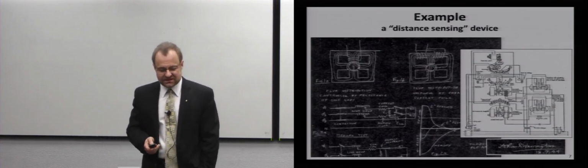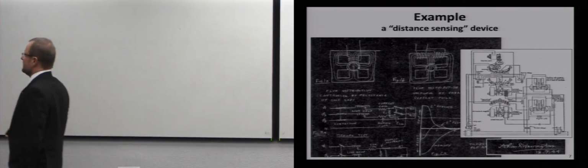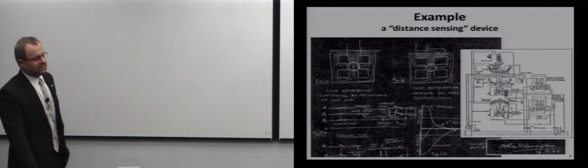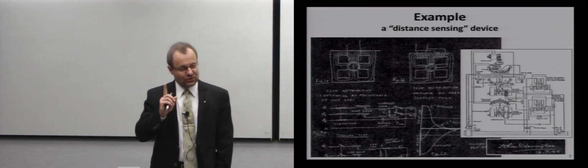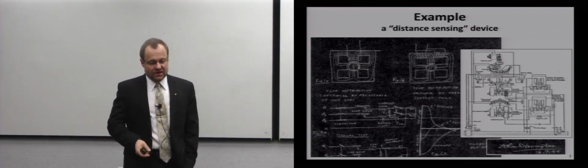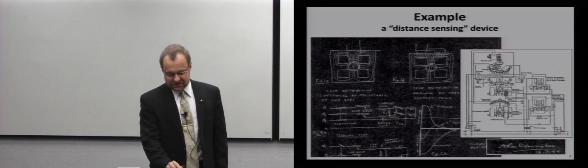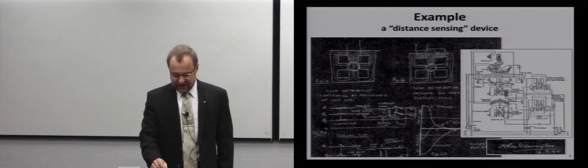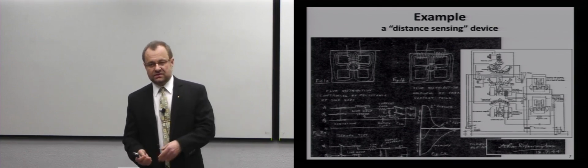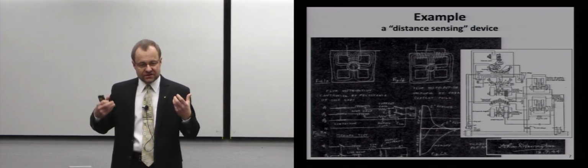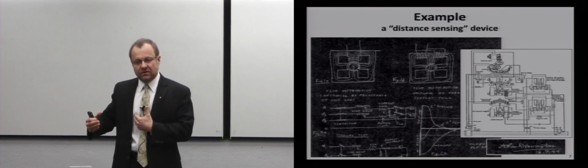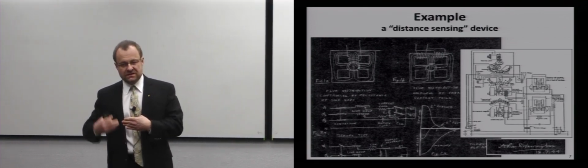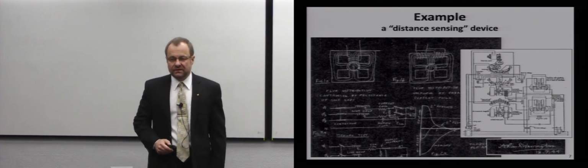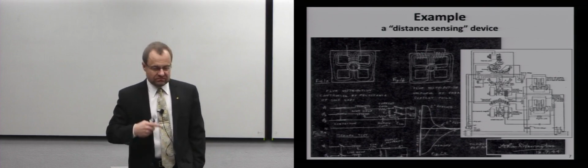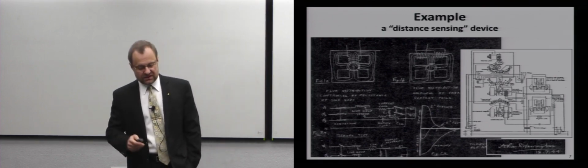So this is an example of a distance sensing device, courtesy of Mr. Warrington, a very known pioneer. You could look at the date. It's 1944. That was the invention. At that time, they had vacuum tubes, but they were too new a technology for this. So as you could see, there is a core, there is coils. You shape that thing properly, like this, and it will behave as something that you hit with a current and a voltage, and it will respond like a distance relay. It will respond to a distance to fault, or an apparent impedance between your CTs and PTs and where the fault is, right? But it wasn't trivial. There was a lot of auxiliary switching, springs, bearings. This thing wasn't accurate, but that was state of the art.